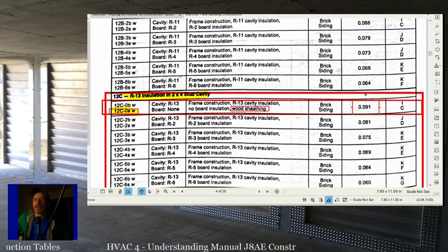The biggest thing is to verify you have some insulation, because if it doesn't have any, you need to account for that. And honestly, remember, your job as a technician is to tell people if they don't have any insulation in that cavity, that before they make big changes to their HVAC systems, they should make energy efficiency changes to their insulation, because that commonly is a better investment. You can get a really efficient system to make up the 120,000 BTUs they're losing, but if you can get it down to where they're only losing 70,000 BTUs, then a less efficient system is still going to be better for them in the long run.